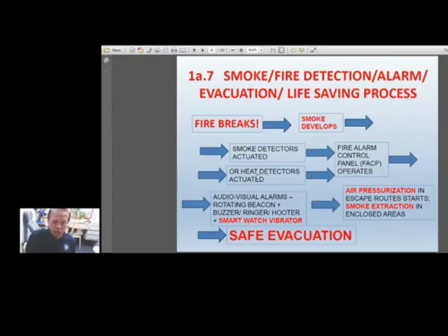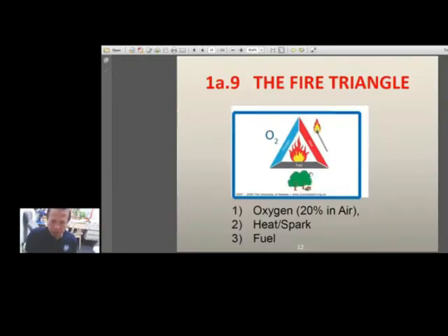Or if extraordinary heat is detected by heat detectors, they will also send a signal to your fire alarm control panel, and your FACP will send a signal to your audiovisual alarm. And of course, this includes the ringer, buzzer, horn, rotating beacon, and so on. And like I said, you can also include the smartwatch vibrator that I mentioned earlier. And you can now actuate your stairwell pressurization so that the escape routes are pressurized. Then smoke extraction can also happen, so that safe evacuation of people from a building becomes possible.